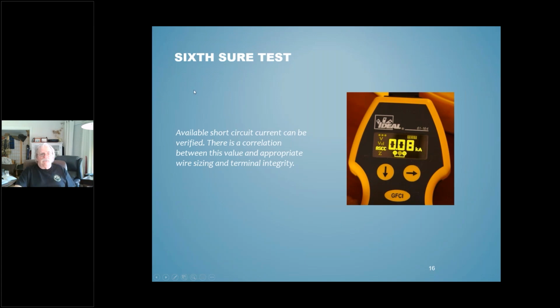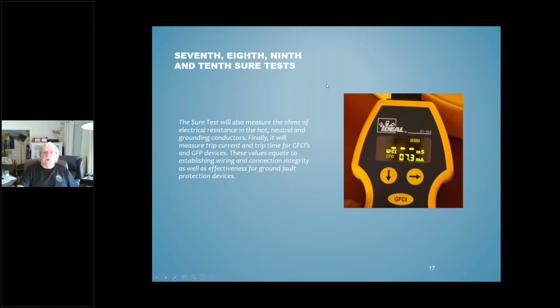Available short circuit current is one that confuses a lot of people. This is a situation where a big number is a good number. Again, wire sizing and terminal integrity is what we're alluding to here. It basically is telling you how much AC current could be delivered to the point at which you're checking it. And a high number is a good number. A low number, again, implies possibly bad connections or undersized wiring. So it's a good test. And then the last three tests are actually checking the capability of a GFCI or a GFP device.